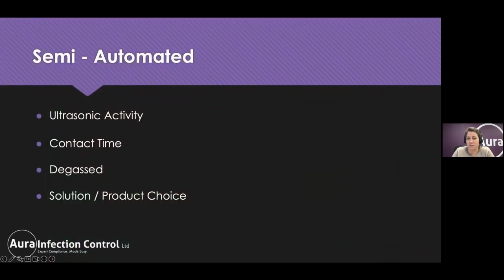The next option is a semi-automated cleaning process, which is the use of an ultrasonic bath. Ultrasonic baths use sound waves, like a high frequency sound wave, to cause disruption and removal of soil from the surface through a process called cavitation. So your items would be initially, before they go in an ultrasonic bath, submerged in a water and cleaning solution, and then subjected to cavitation. And you need to follow your manufacturer's advice and the evidence from your validation testing to support your decision about the most appropriate cycle time.